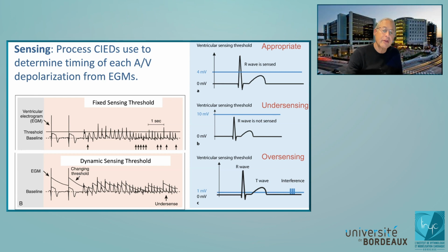Additionally, there are two classes of sensing thresholds. There are fixed sensing thresholds where we just set a constant value for sensing, and that's used in many older pacemakers. And here we see an example of the onset of ventricular fibrillation with quite a bit of undersensing. Alternatively, all implantable defibrillators and many modern pacemakers use some form of dynamic or time varying sensing. And the way this works in principle is that the sensing threshold increases after each sensed or paced event. And then the sensing threshold decreases over time afterwards if there is no sensed event. And so this helps us avoid T waves, but if ventricular fibrillation starts and it misses one fibrillatory wave, it will find the next one.